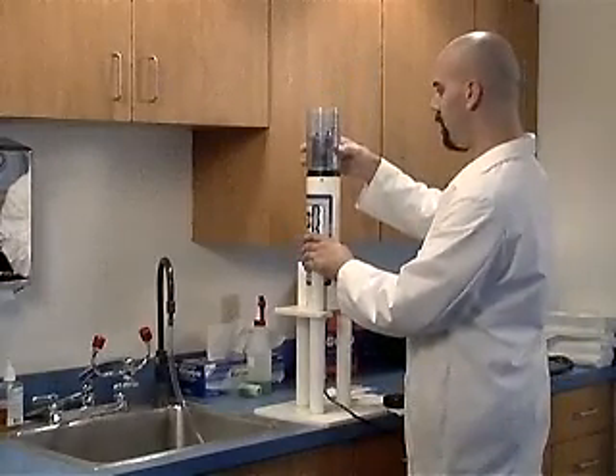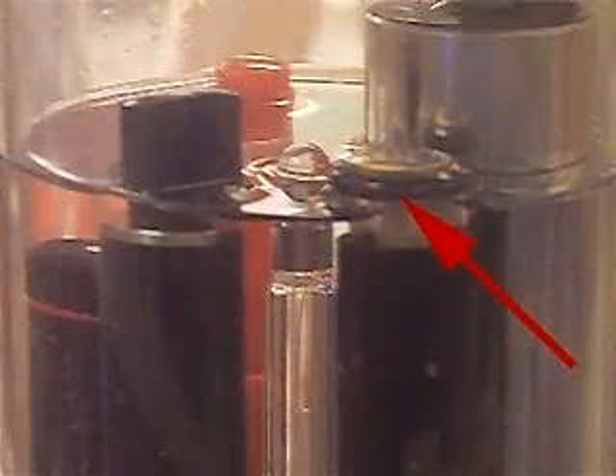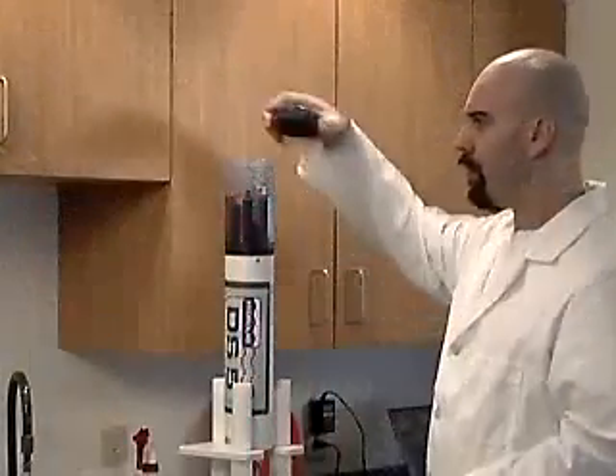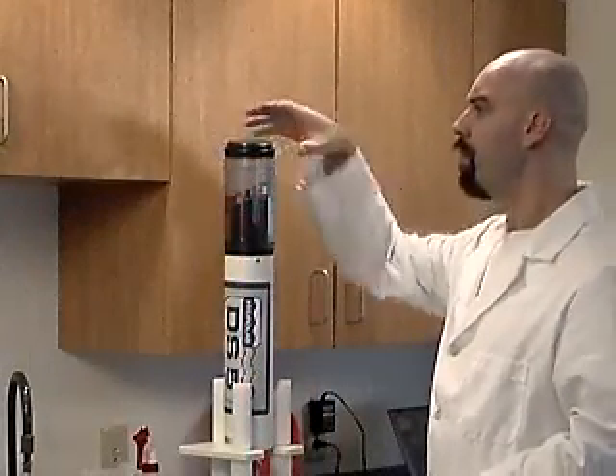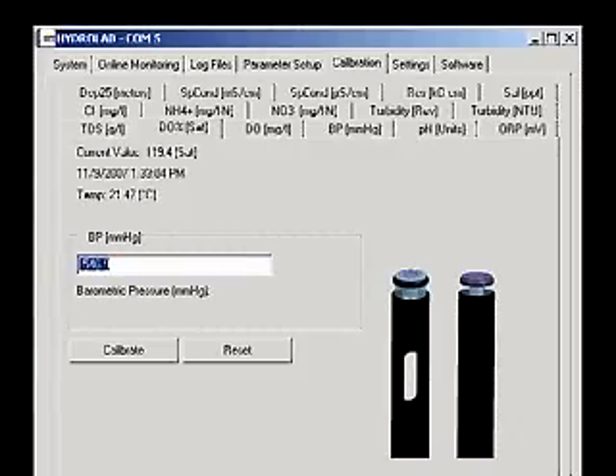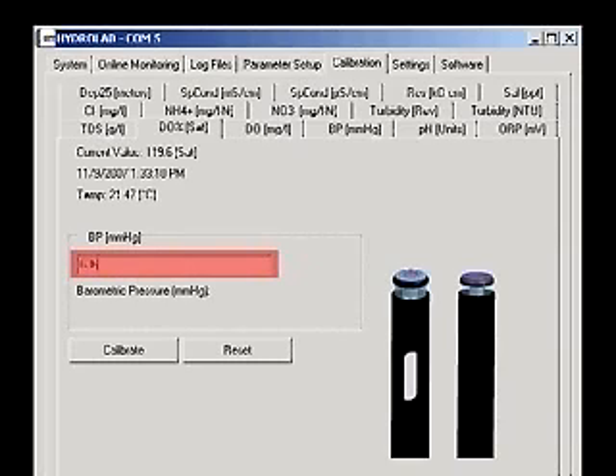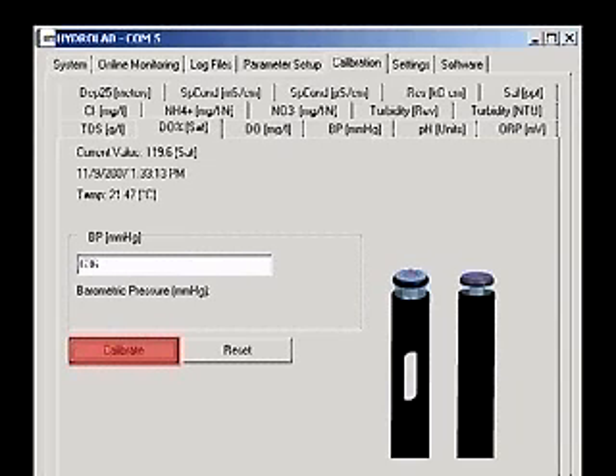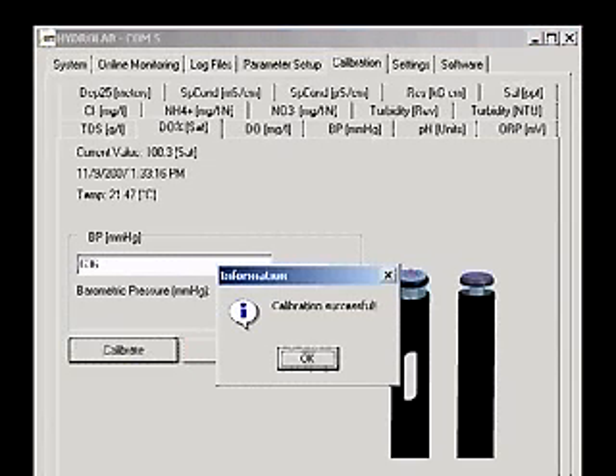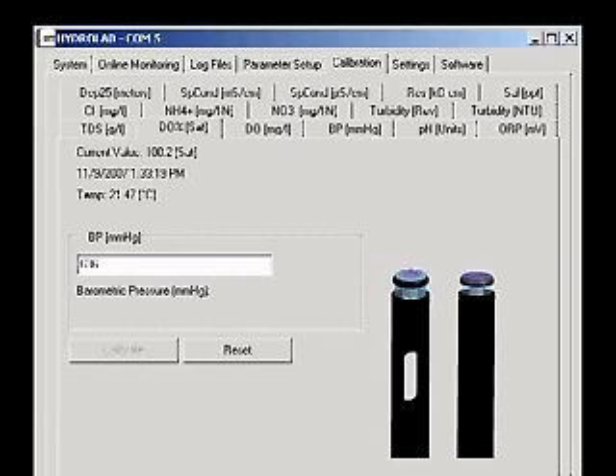Rinse the sensors with clean water and install the calibration cup. Fill the cup with water until the level is just to the bottom of the O-ring. Remove any drops from the top of the membrane. Place the storage cap over the top of the cup, upside down. Wait for the current value to stabilize. Enter the current absolute barometric pressure in the box and click the Calibrate button. A calibration successful message will now appear. The Clark cell dissolved oxygen sensor is now calibrated.